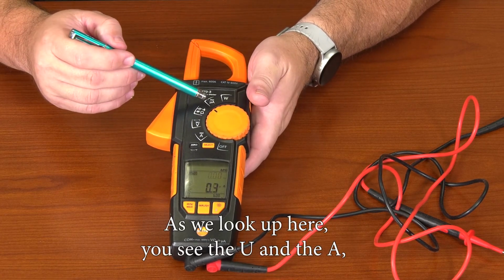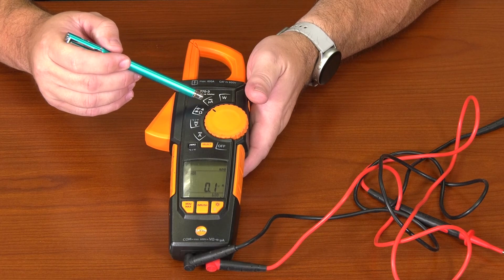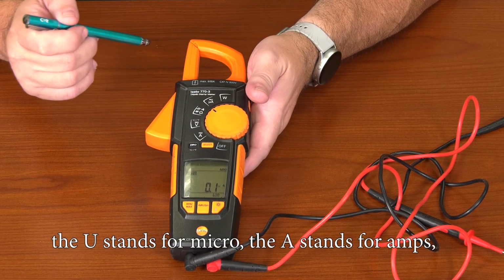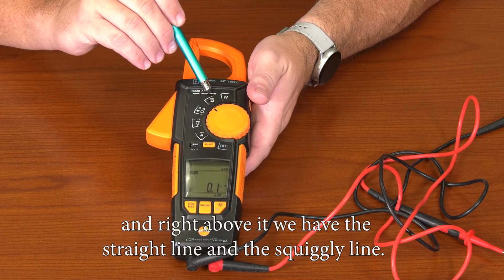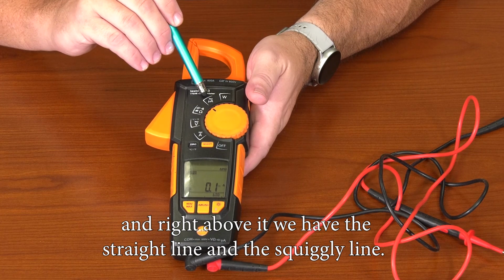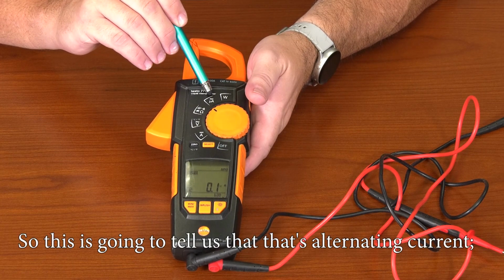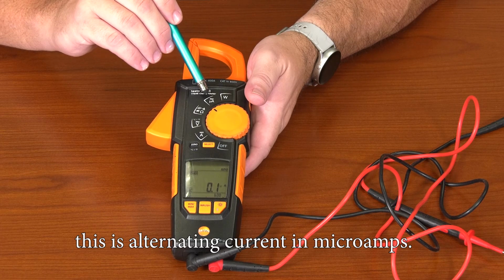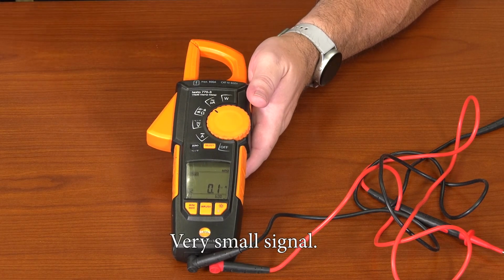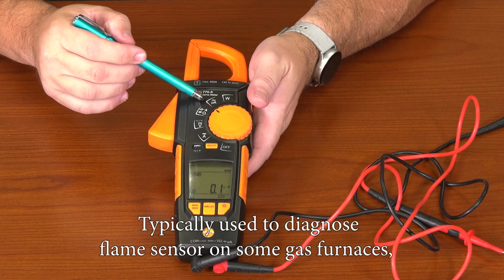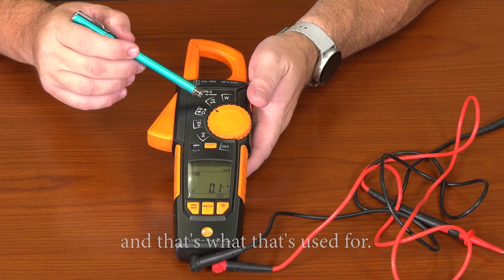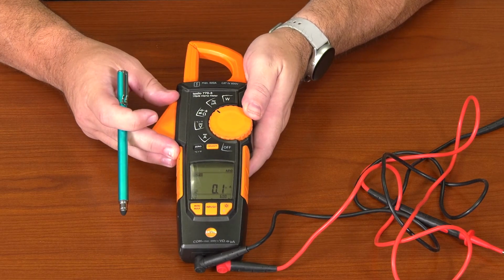As we look up here, you see the U and the A. The U stands for micro, the A stands for amps, and right above it we have the straight line and the squiggly line. So this is going to tell us that that's alternating current. This is alternating current in microamps. Very small signal, typically used to diagnose a flame sensor on some gas furnaces, and that's what that's used for.